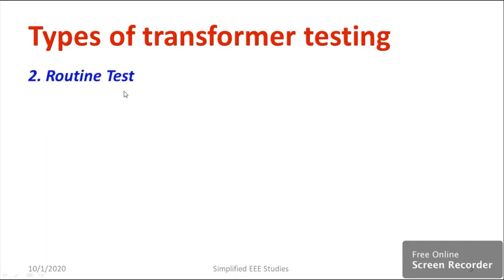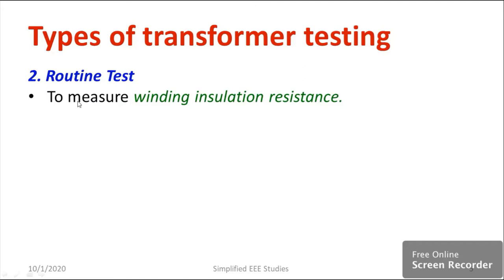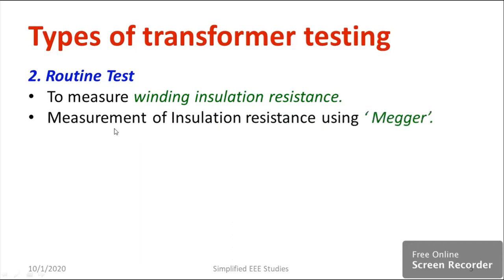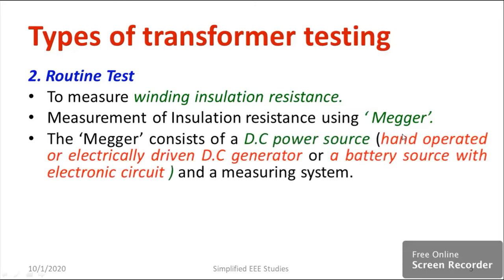I would like to discuss about routine testing. The main purpose is to check the winding resistance and insulation resistance of the transformer. Measurement can be done with the help of a device known as a Megger. There are two types: a hand-operated or electrically driven DC generator type Megger, which is conventional, and nowadays it is replaced with a battery-operated Megger with an electronic circuit.